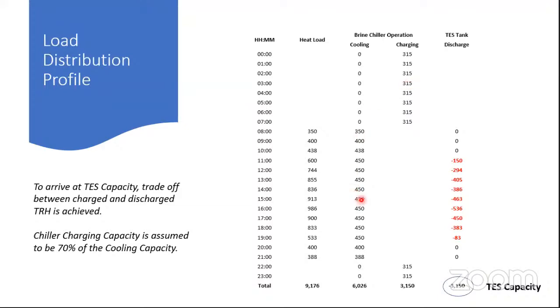first I'm making my chiller run in a cooling mode. I'm making my chiller run at 5 degrees centigrade. That is for cooling, and then when I'm charging it, I'm making it run at minus 5 degrees centigrade. So I am making my chiller go down further in terms of supply temperature, so my chiller will be able to deliver lesser tonnage. This is the deration that happens on account of charging when compared to cooling capacity.